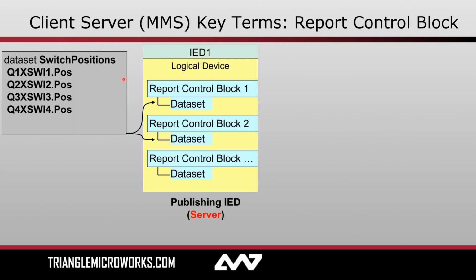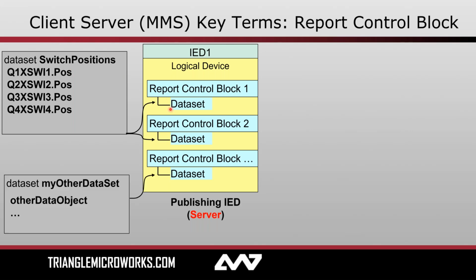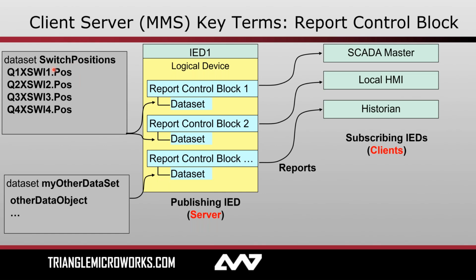Now note that I have this single data set linked to multiple report control blocks, and I might have a different data set linked to another report control block. Now, the reason I might have the same data set linked to multiple report control blocks is because while there's not a one-to-one relationship between clients and servers, there is a one-to-one relationship between a client and a specific report control block. At any given time, only one client can have enabled and received data from a specific report control block. Now, there are cases where you can instance a report control block, in which case the same report control block exists multiple times, kind of like what we have here with the same data set being passed into multiple control blocks.